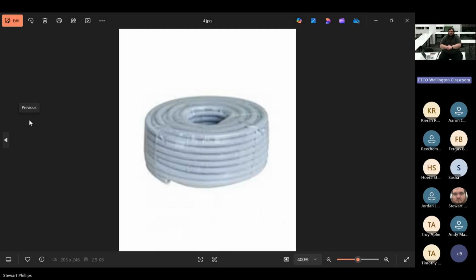Cool, and this is your corrugated or flexible conduit. It's very good for running around those tight and strange kind of corners and angles. There are some guys out there who just exclusively use flexible. They don't even bother with rigid or solid conduit. They just run everything in flexible. And it looks like absolute dog shite. Yeah. I would rather use straight runs where I can, and bends. Yes, it does degrade faster and it is more susceptible to mechanical damage.